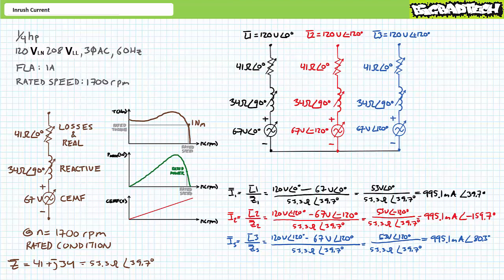In summary, the current drawn by a motor reflects not only the magnitude of the real and reactive components at that specific operating condition on the speed-torque curve, but also the amount of counter-electromotive force experienced at that rotational speed. At higher rotational speeds, the winding experiences more CEMF in opposition to applied voltage; at lower rotational speeds, less. At zero RPM, the winding experiences no CEMF in opposition to applied voltage, and it is this phenomenon above all others that explains the intense but brief surge of current known as inrush.